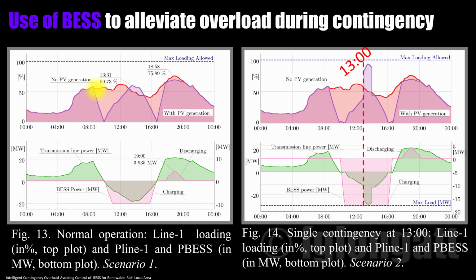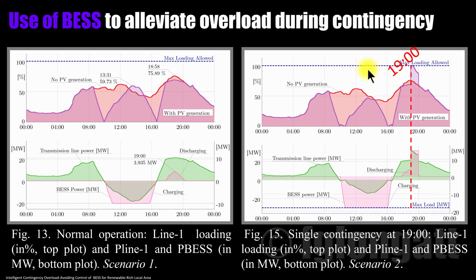For instance, here on the right-hand side, you can see that the contingency is happening at 1 p.m. As you can see, suddenly there is an increase of the loading, but at the same moment, the battery energy storage is charging. As a consequence, this very specific charging has been optimized to reduce the overloading on the transmission line. And in this condition, before we installed the intelligent battery energy storage system, in the previous condition there was overload. Right now, the loading is below 100%. But now let me do it in another moment.